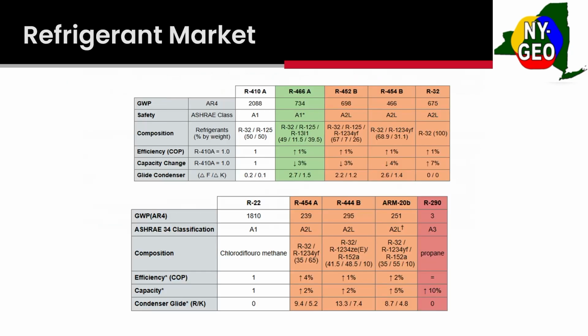So here's a quick snapshot of the refrigerant market. Here you can see we've got 410A on the left. We've got COP and capacity change. So if we look at 454B, slightly more efficient, a little less capacity. So that's why if you've spec'd any new 454B rooftop units or residential splits, the equipment is much larger. The evaporator coils, condenser coils need to be larger for greater heat transfer. R32 is a 100% pure refrigerant, and you can see this is much more efficient and has a higher capacity change, and that's why you're seeing R32 for a lot of VRF systems.